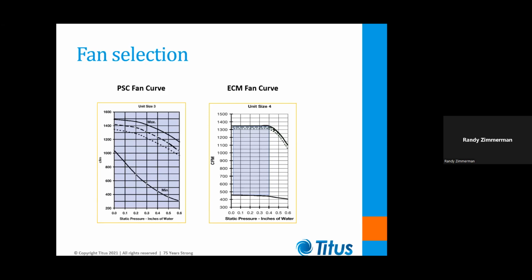The ECM is very different. You can see it's very flat over much of its operating curve because it's programmable, and most people program their ECMs to automatically compensate for changes in external pressure. So they do compensate up to a certain point at which they start to run out of horsepower, and then the curve noses over. ECMs don't really have a minimum curve, but most manufacturers program a minimum speed curve into their motors to prevent them from getting into situations where the motor may have trouble stabilizing, where it runs roughly at the low end. So we try to program a minimum curve that allows the motor to run smoothly.